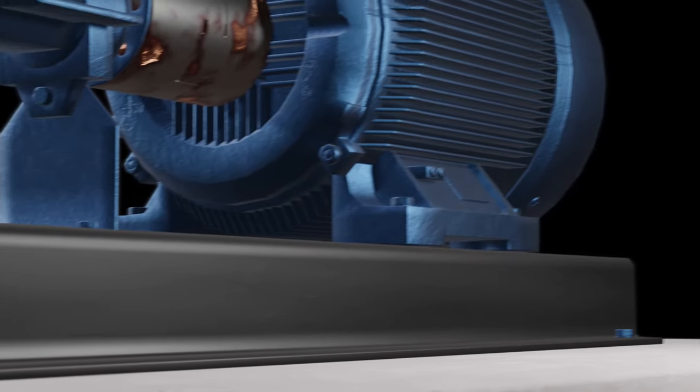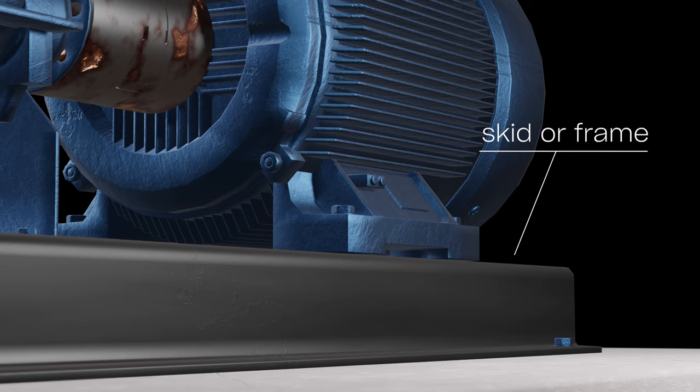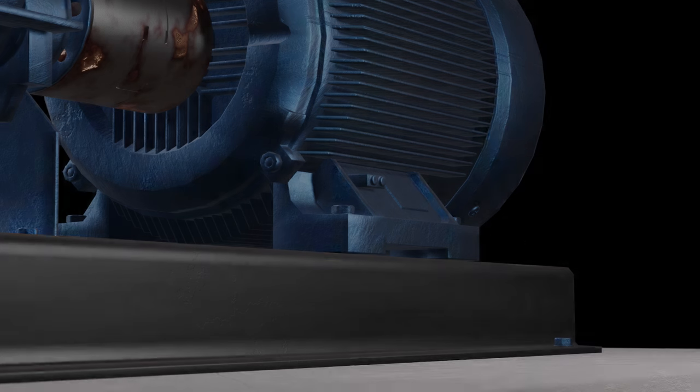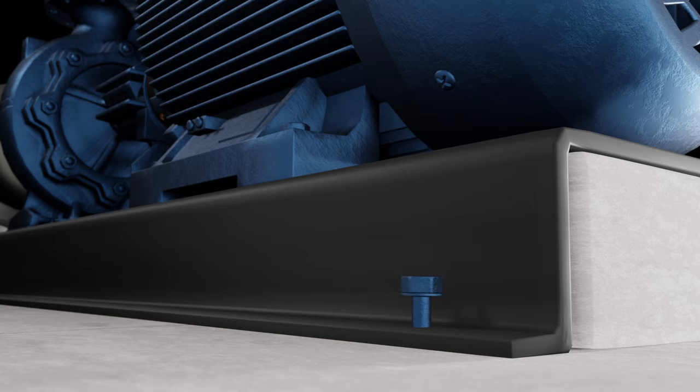Next, make your way upwards to the skid. The skid or frame should be solidly bolted to the base. During your inspection, confirm that all bolting is tight.